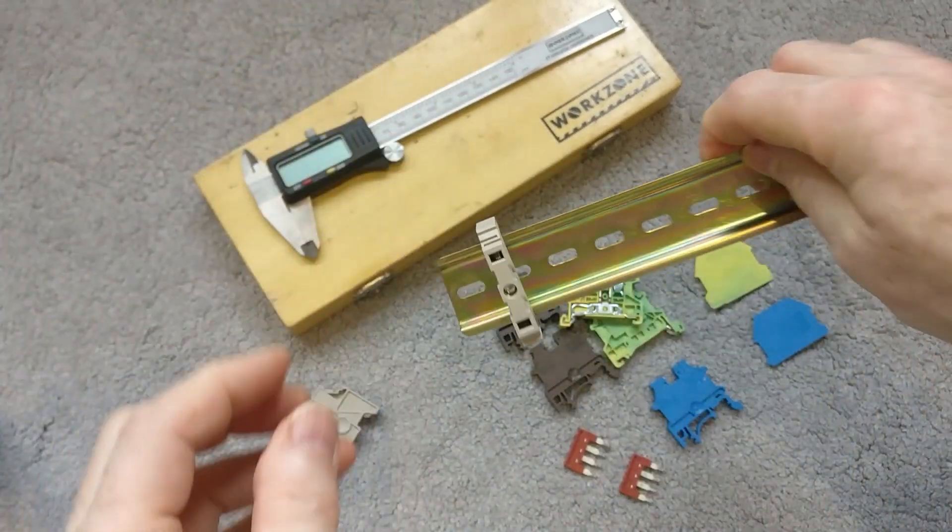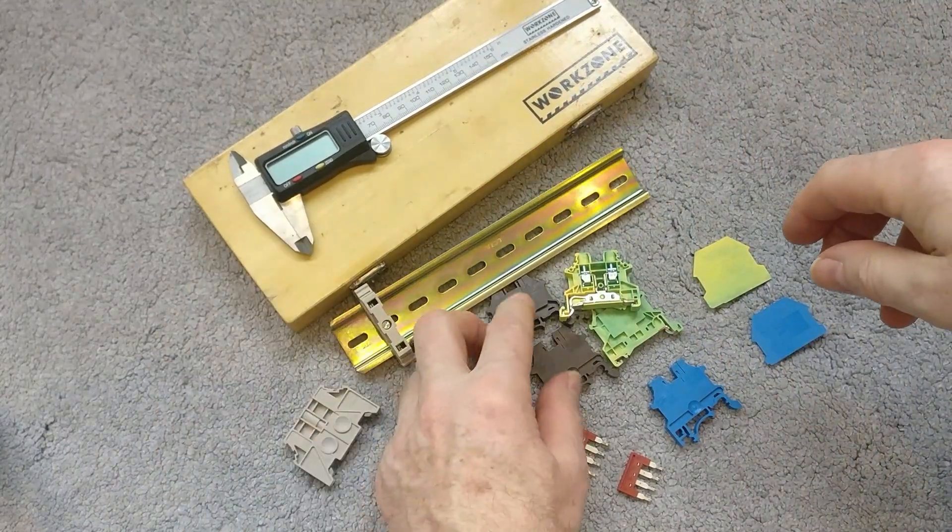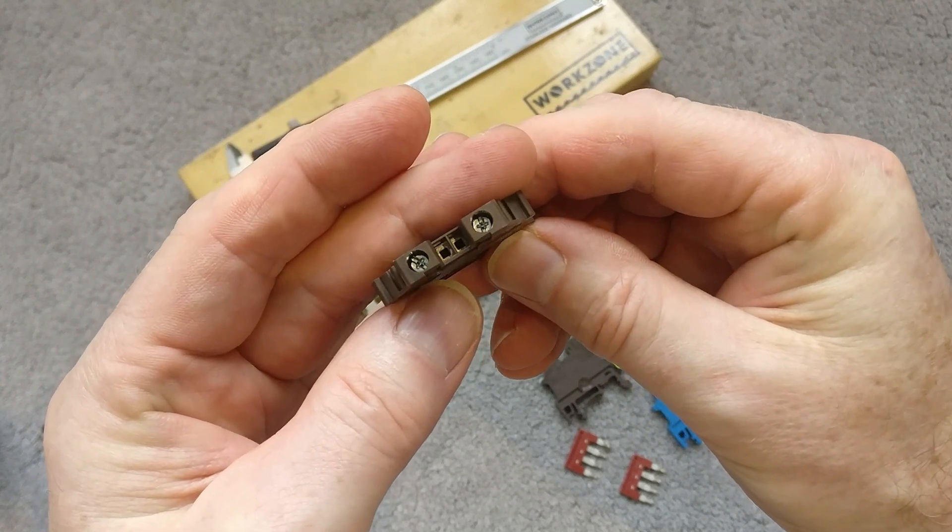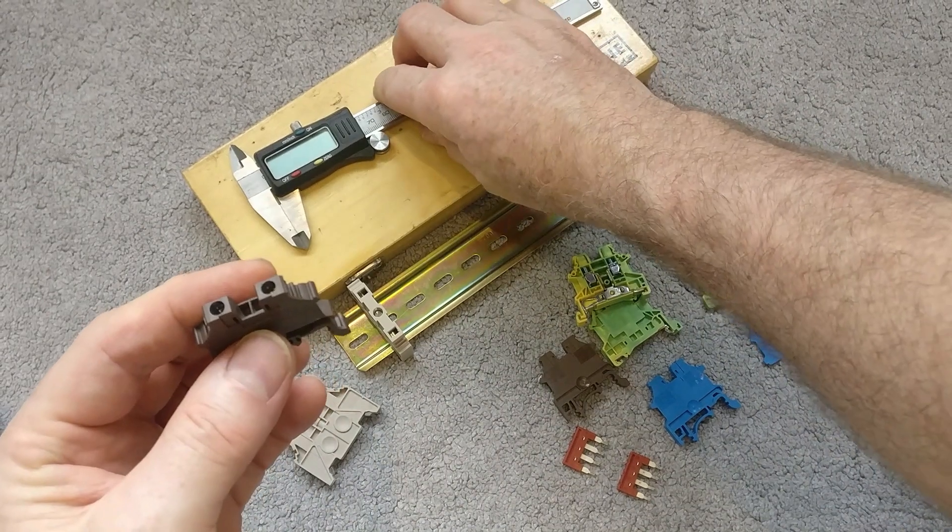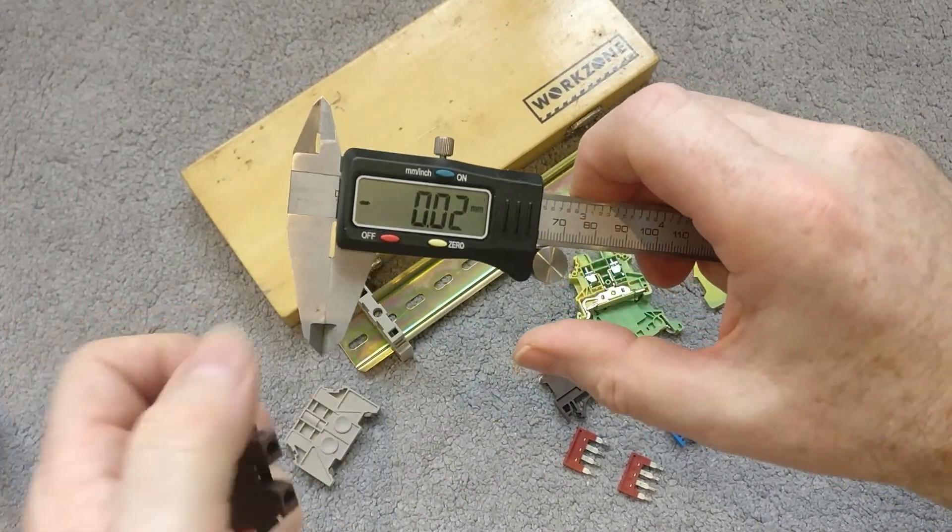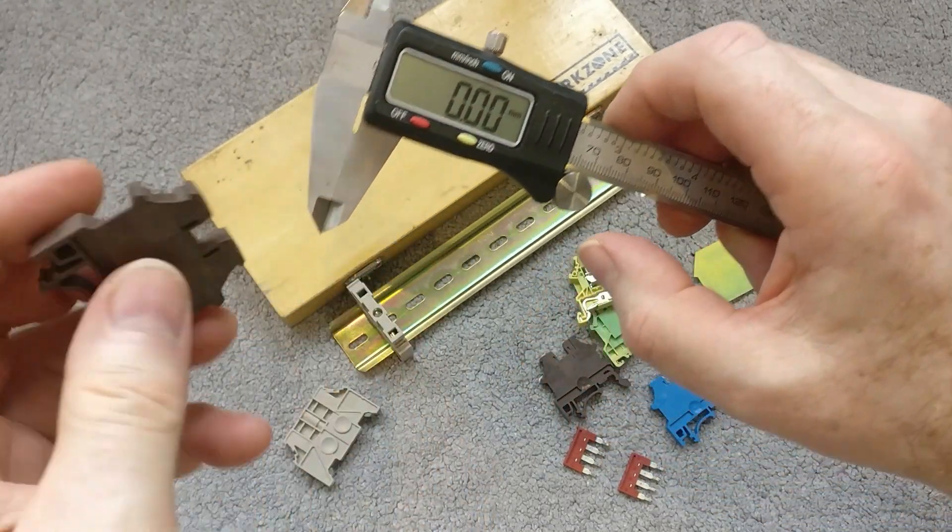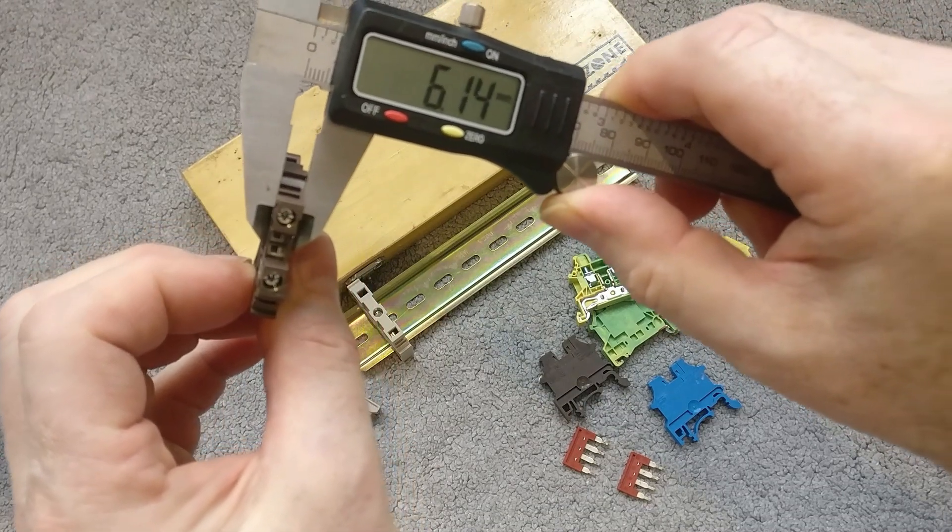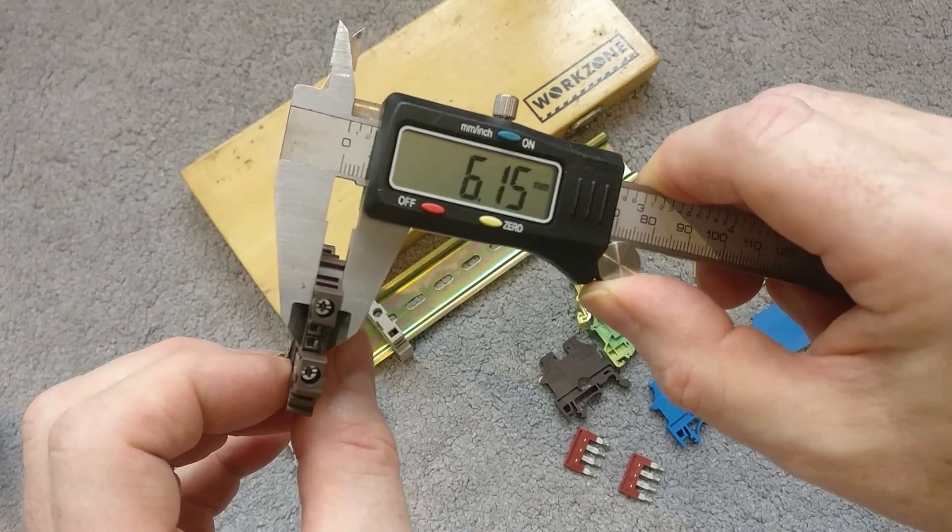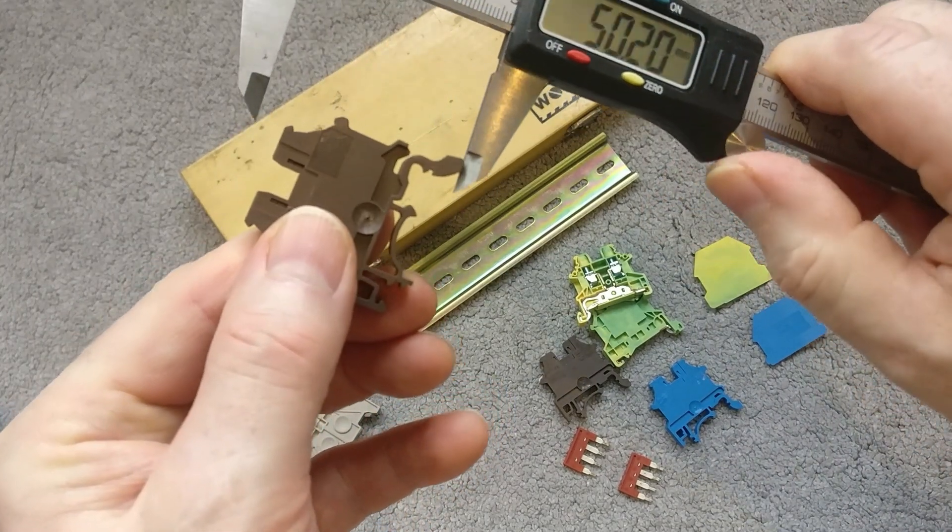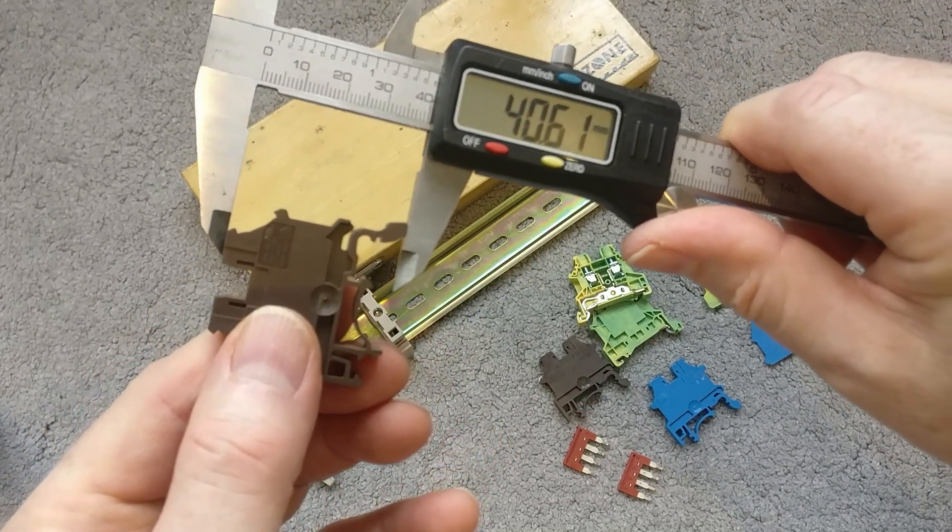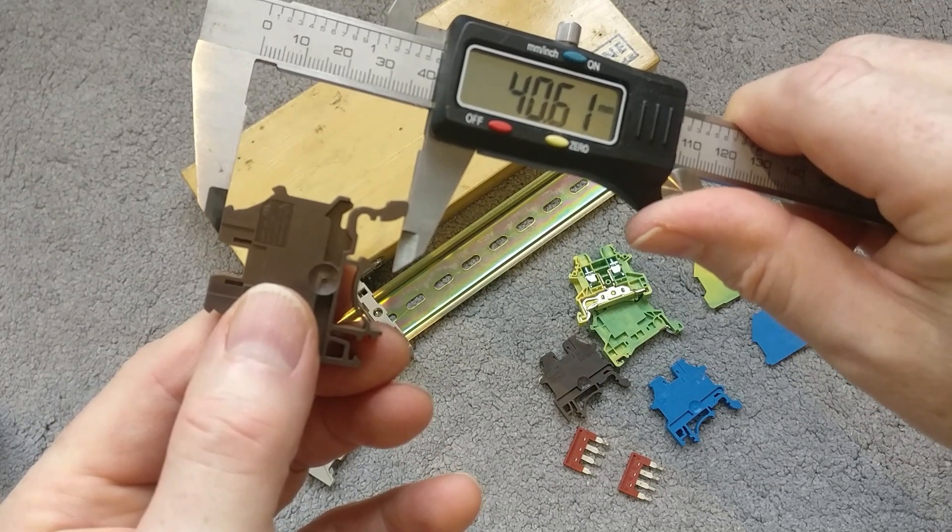So let's look at what the sizes look like. This is a 4mm squared connector, so this carries about 30 to 32 amps. Let's just look at the measurements. The thickness is 6.14mm, and the height in total including that spring block is about 40mm, so you need to take that into account if you're putting this inside a junction box.